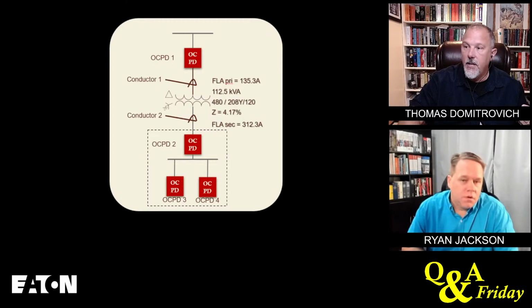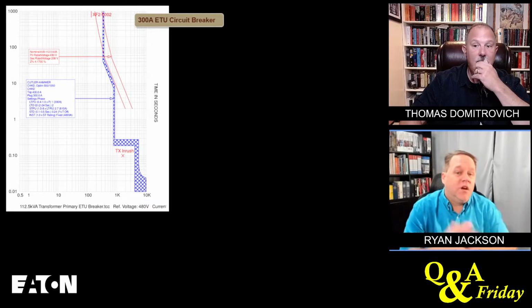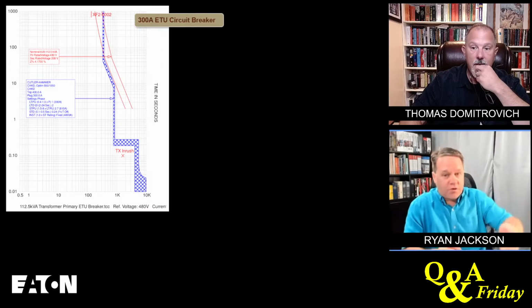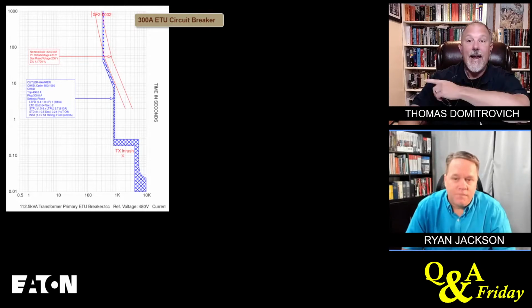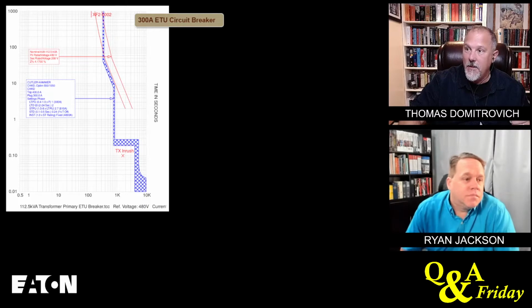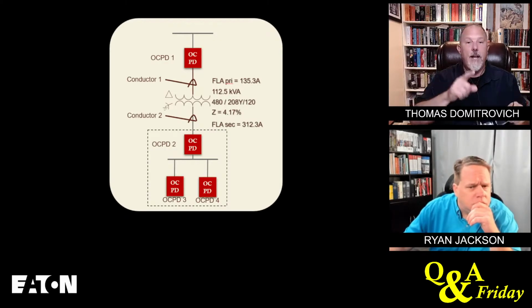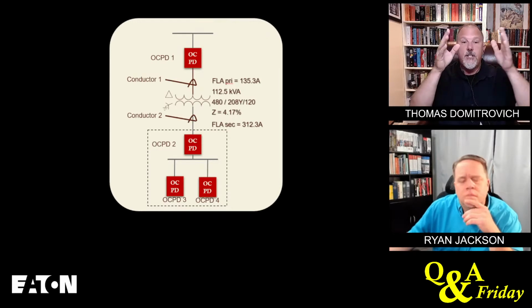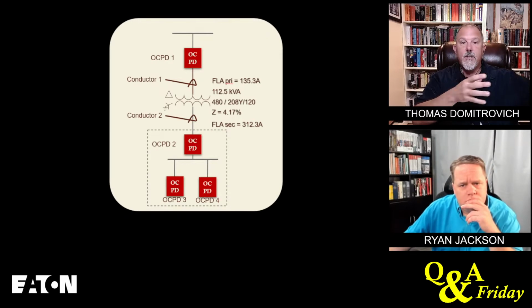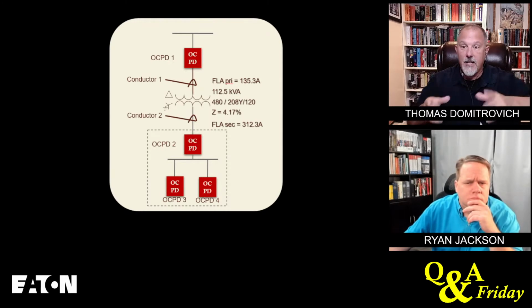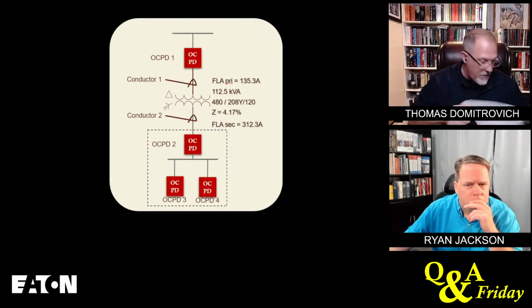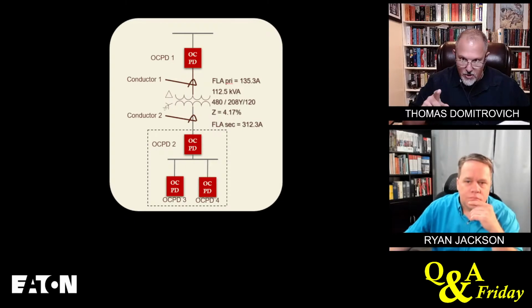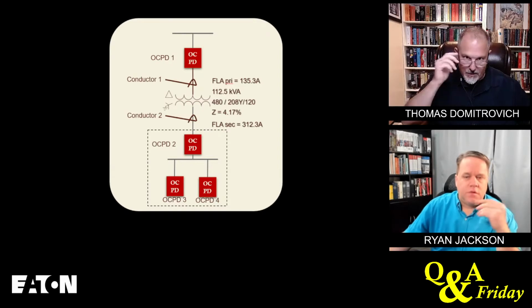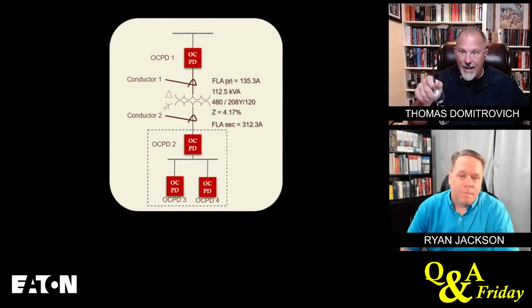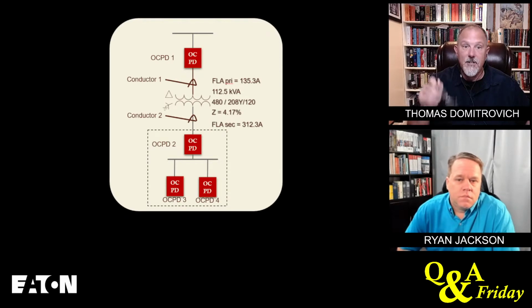Right. Yeah, I totally agree. The most incident energy you're going to find is usually at the service equipment or transformer secondary. Right. So let me ask you a question. When I pick the primary overcurrent protective device, does a transformer that has a primary overcurrent protective device that protects the secondary, because it's a delta, right? That's one condition. Delta transformers, I'll just say delta. Let's say it's a delta, a delta that's not a high leg. That's not a high leg, correct. Does a delta transformer have inrush current like a delta-Y ground transformer?